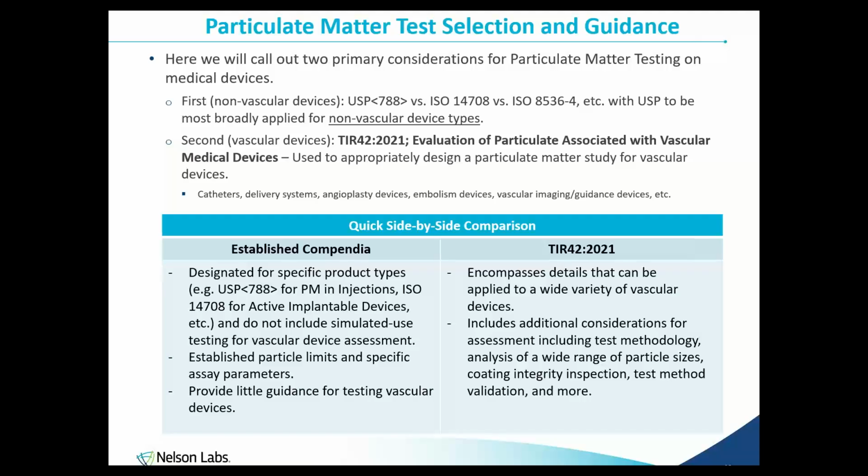If we shift over to TIR 42, this encompasses a very wide variety of vascular devices: catheters, delivery systems, vascular imaging devices, embolism devices. It allows for a framework where, if you have a vascular device, you can create a test system and dive a little bit deeper into the particle shed and what that means for your product.